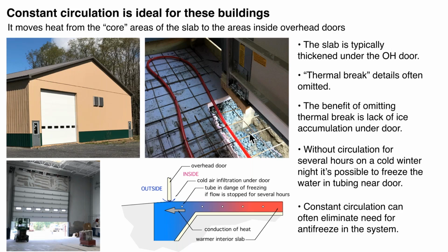And that can be a nice benefit because the heat transfer that goes out through that concrete by conduction actually prevents ice from forming under that door and freezing the door down to the slab. And it does melt the snow just a few inches out. But this is the downside of this. Imagine if we had controls on the system and we had a deep thermostat setback at night, water in the tubing, and imagine that it's 15 or 20 below zero out, which is possible where this building is located, and there's no flow going through that circuit for, let's say, 10 hours or 12 hours, it will freeze.